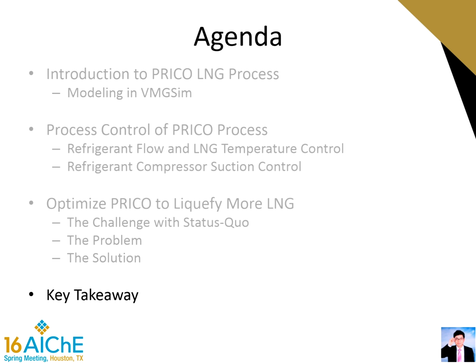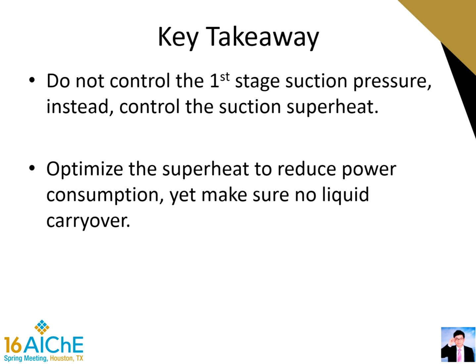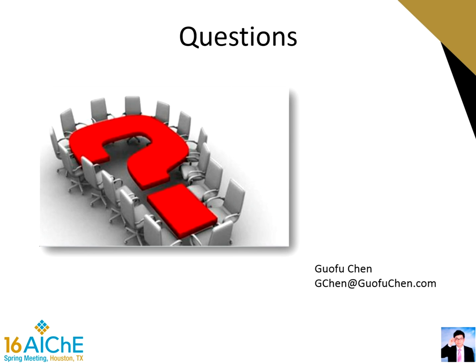We now come to the final conclusion. For a typical PRICO LNG process, please do not control the first-stage suction pressure. Instead, control the suction superheat by manipulating the pressure throttling valve. There may be room to further optimize your PRICO LNG plant by optimizing the superheat, but please make sure there will be no liquid carryover to the compressor. I'm sorry for not being able to take your questions or comments in person. Please email me at jichan@guofuchan.com. Thanks for your attention.